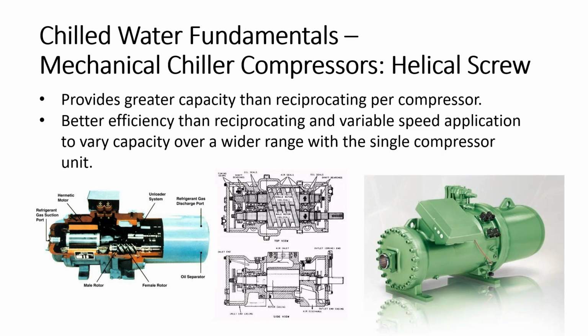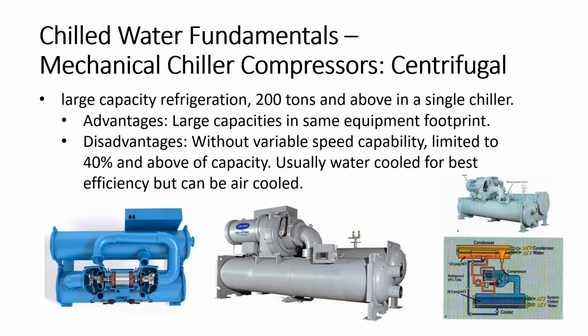Now we have kind of a marriage of scroll and rotary called the helical screw compressor. These are more efficient than the reciprocating. They have better efficiency than reciprocating in a variable speed application, and you can vary their capacity over a wider range with a single unit. You saw the comparison of the air-cooled reciprocating versus the air-cooled rotary, helical screw, sorry. You had fewer compressors in the air-cooled helical screw. So you can actually do the same capacity with fewer compressors, but you also have better control over the range of capacity with these, because you can put them on variable speed drive. They have very efficient compression ratios, and so they're just an upgrade on the compressor side from both rotary and the reciprocating.